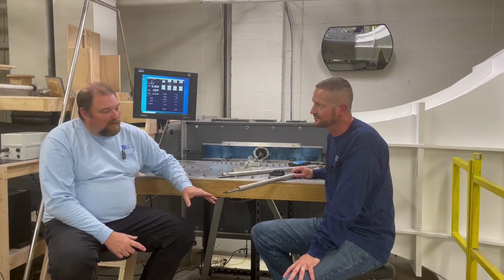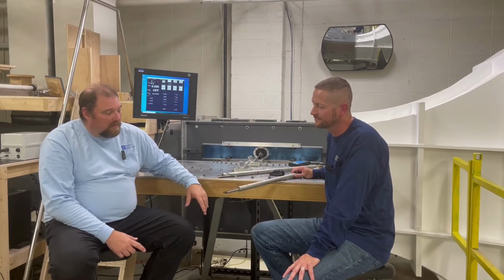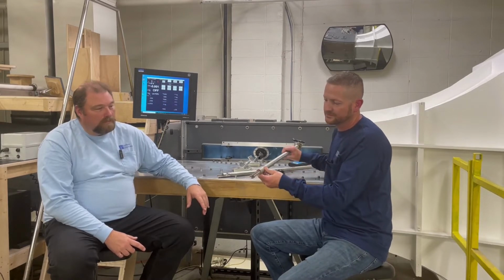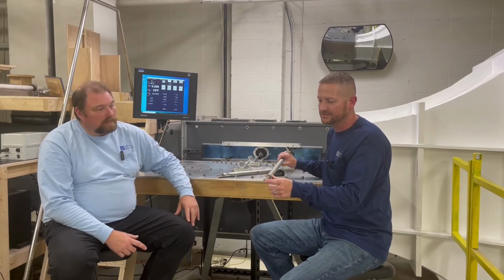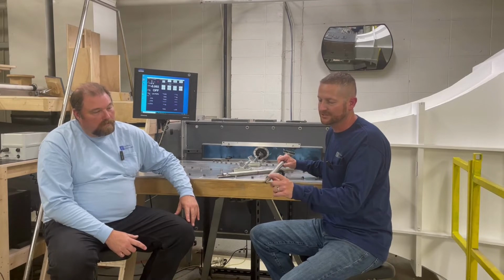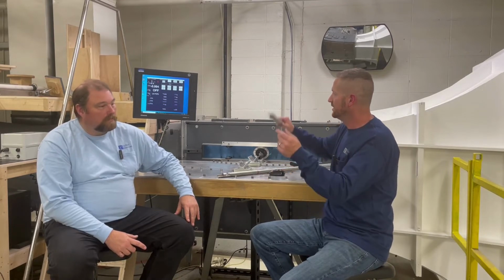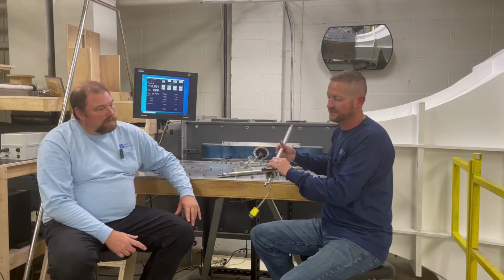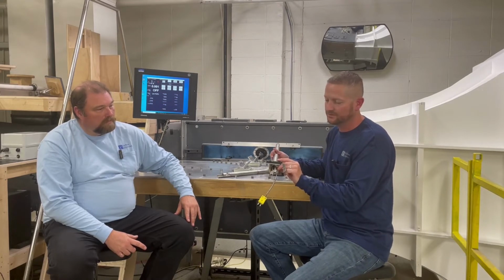For people who aren't familiar with the probe, would you mind going over some of its features? This probe offers a bump stop, a high pressure side, low pressure side, and a K-type thermocouple. On the back, we also have a level to make sure you're level with the flow, and we have swagelok fittings.